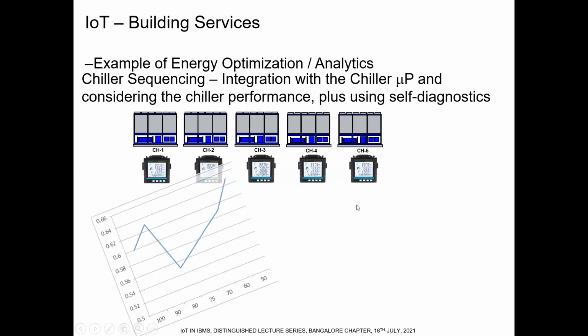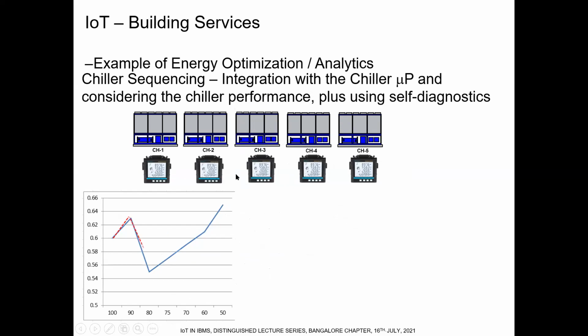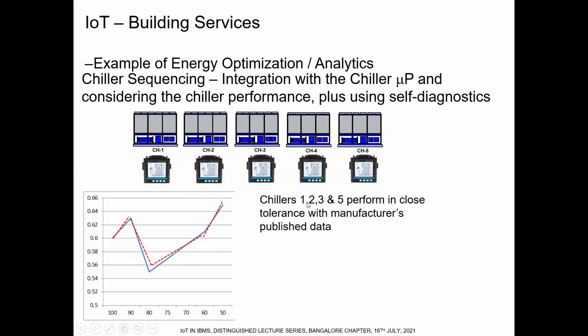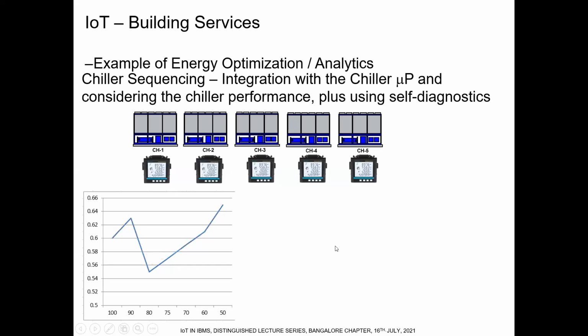And then we have this sophistication called IoT. So what we are doing is taking the same microprocessor data, because now we are tracking the performance of the chiller. The cloud can plot this data on a one-on-one basis and then track these chillers. The actual performance is the red dotted line. This is very, very close to the blue line, which is given by the chiller manufacturer. Now, the analytics has seen that chillers 1, 2, 3, and 5 are performing in close proximity to the manufacturer given data. So whenever the BMS is doing sequencing, when the next chiller is called upon, there is no hesitation in calling upon chiller 1, 2, 3, or 5 as the next chiller. No problem.